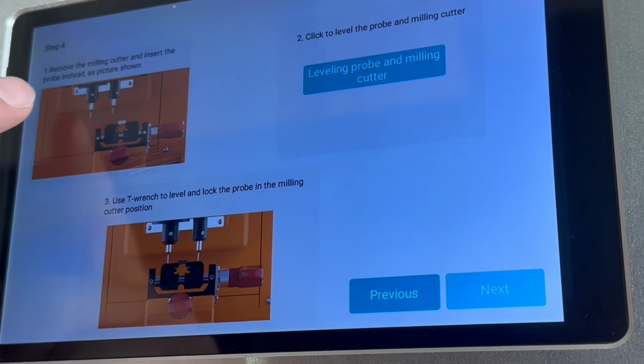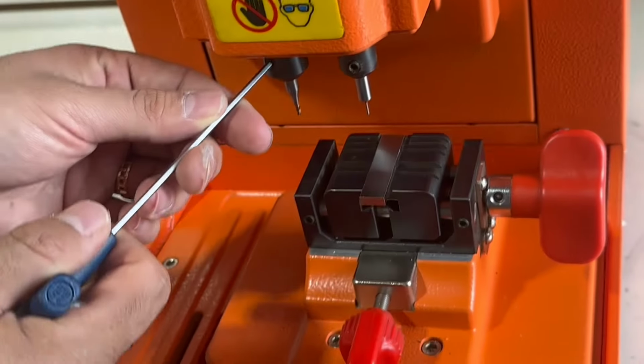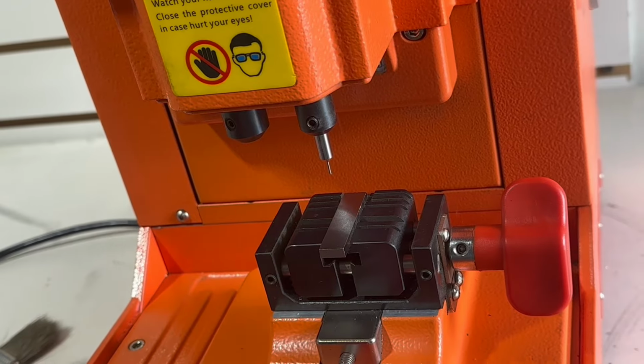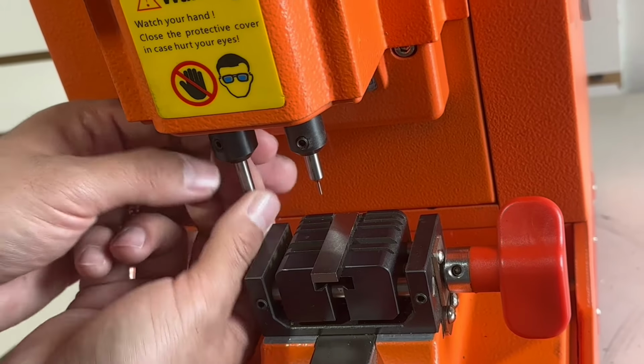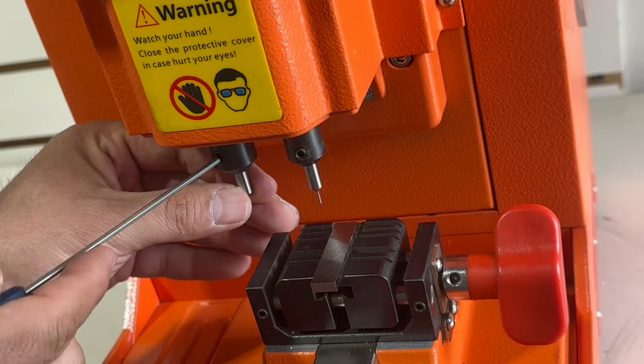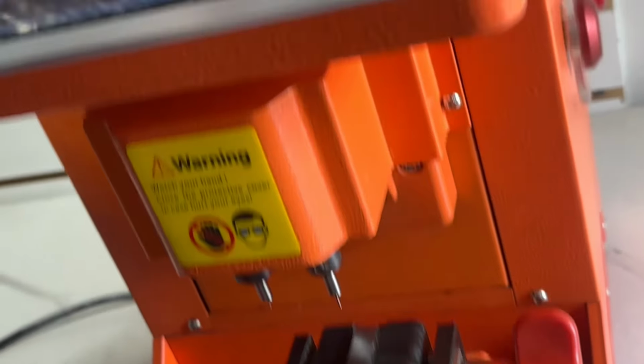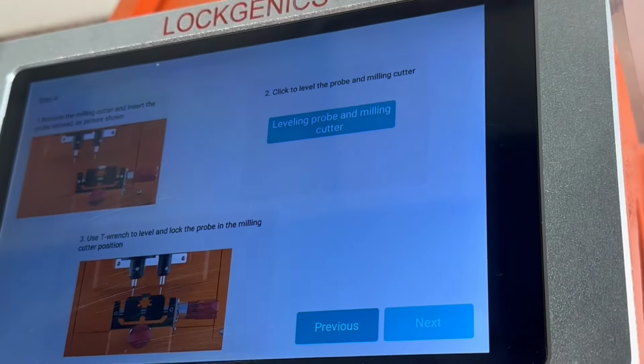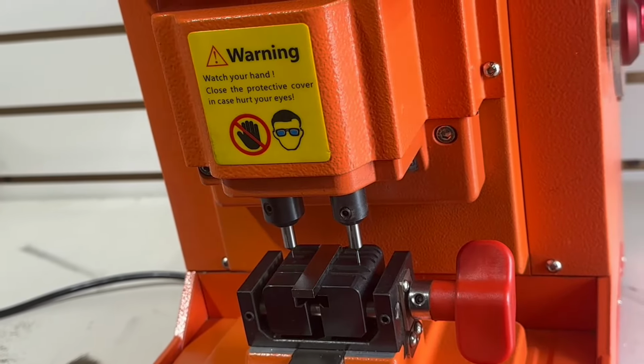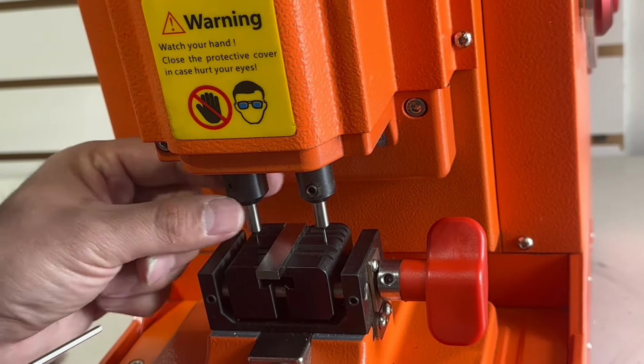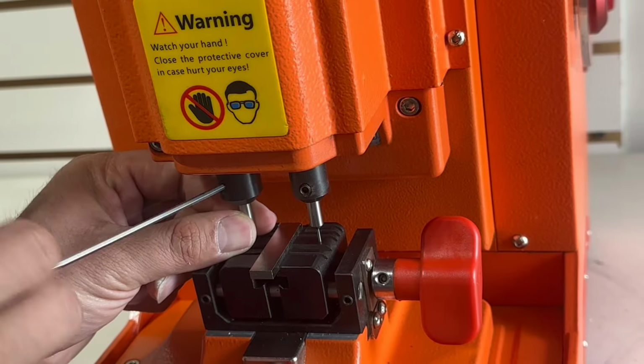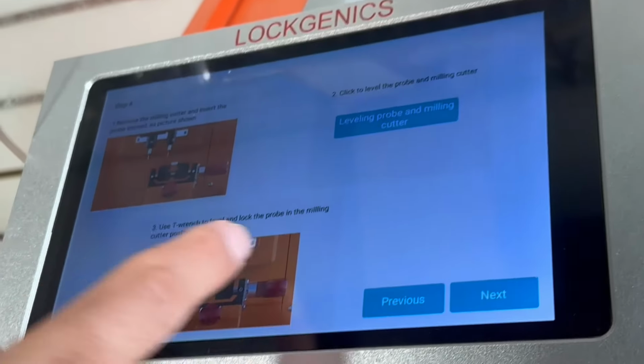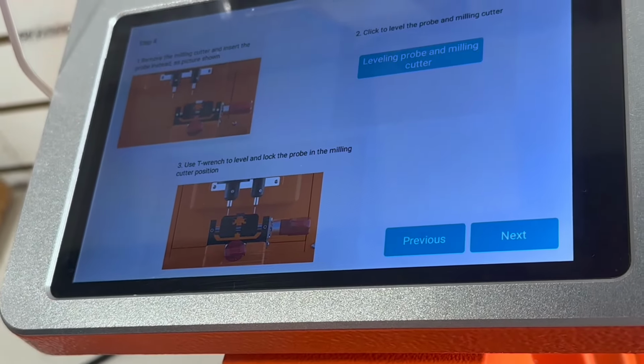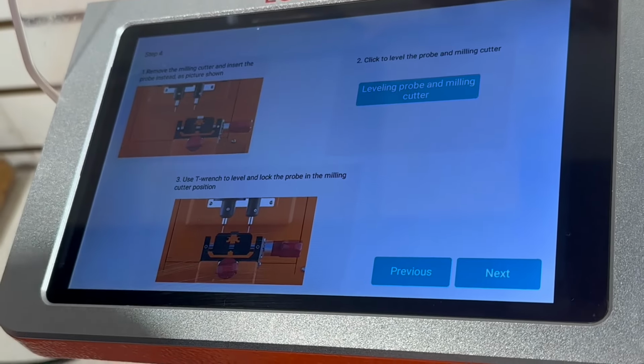And step 4, first step in step 4 is that remove the milling cutter and insert probe instead. So we're going to remove this one. Then we're going to put the probe however way you like to put, doesn't matter, you just need to insert it and tighten just a little bit. And then next step is click the leveling probe. So now it's gonna do the leveling again, but this time for probe. Okay, so loosen again, bring it down, make sure it touches, and then tighten. Once that's done, it says use the T-wrench, which is just saying that we have to tighten and level the milling probe to the cutter position. So it has to be touching the stage. Now you're gonna go next.